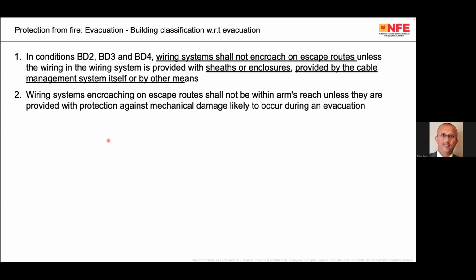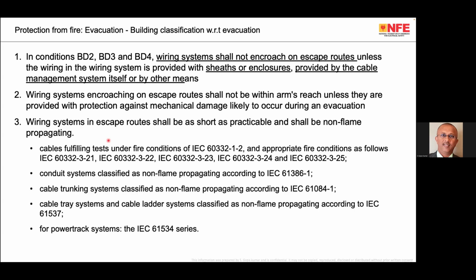Wiring system encroaching on escape route shall not be within arm's reach. That means, even if there is a wiring system in the escape route, it should be 2.5 meters away from the ground, unless they are provided with protection against mechanical damage likely to occur during an evacuation. The materials used: wiring system in escape route shall be as short as practical and shall be non-flame propagating.